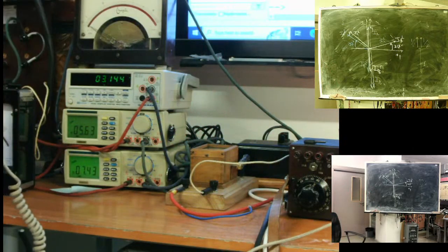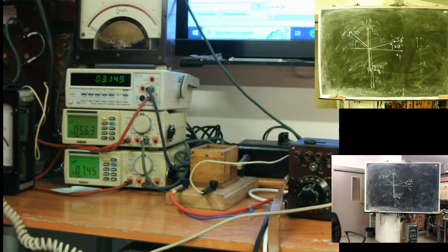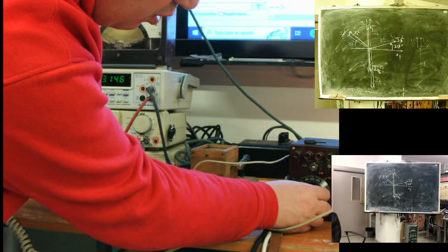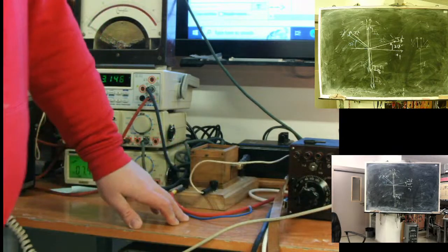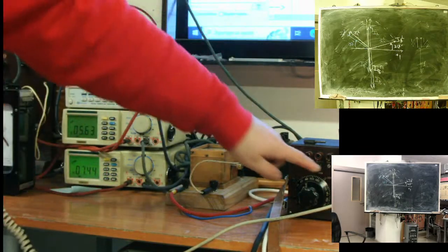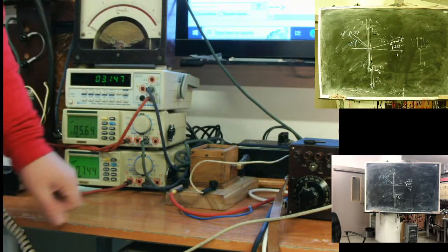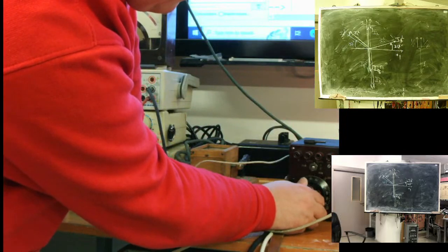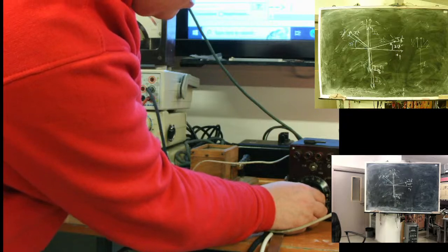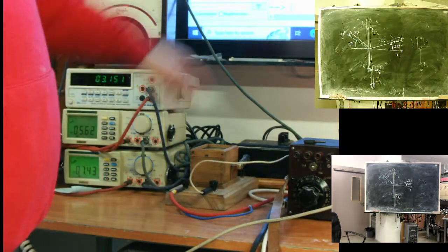And here we are, A phase. A phase has a magnitude of 3.2, should be 2.8, I see 3.2. Its angle is something like 35 leading, 37 leading, possible.